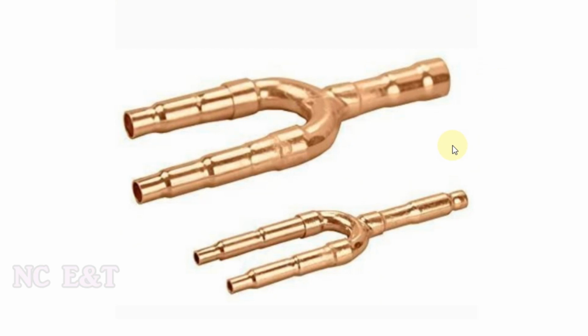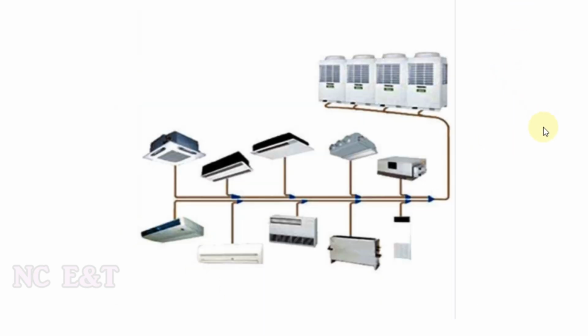So each manufacturer of the VRF system makes their own Y as per their design and supplies it with the VRF units. We know in the VRF system, a large number of indoor units can be connected through a single piping network to the group of outdoor units. But in practice, we don't normally see this. In a single building we have many VRF circuits. It is because there are certain rules that decide how many circuits we need to use and what sizes of refrigerant piping we need to use. We will discuss it with one example.